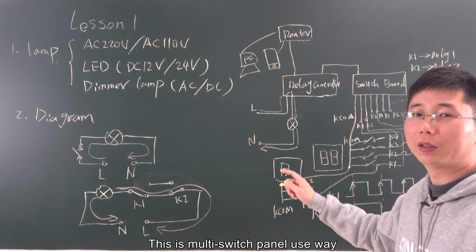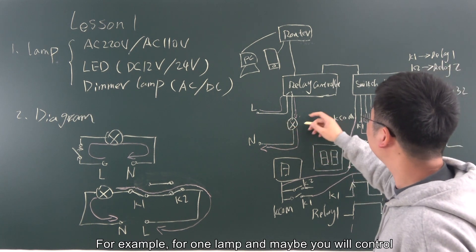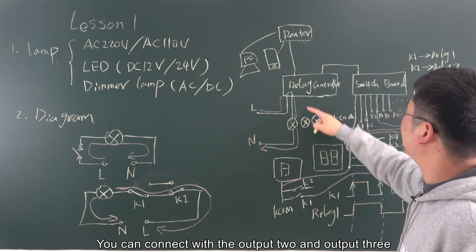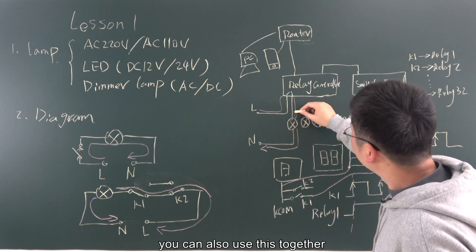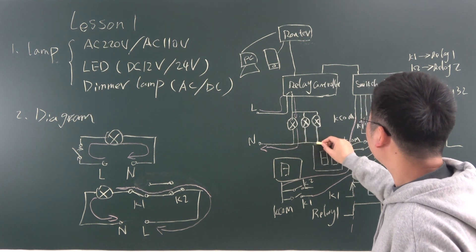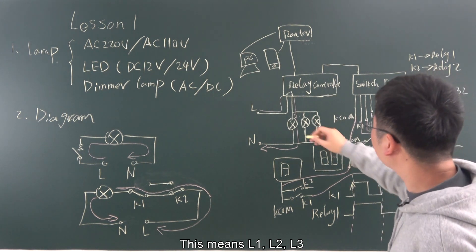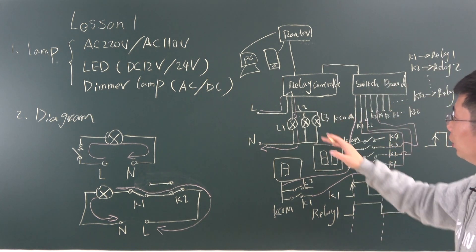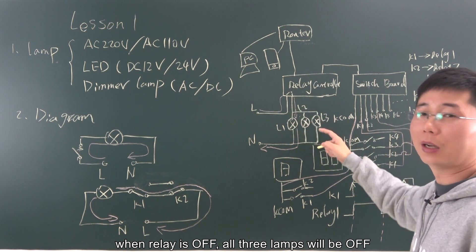Okay, this is multi switch panel to use the way. And if you want to control more lamps, this we have for example for one lamp. Maybe you will control two lamp or three lamp. This is the relay output 1. You can connect with the output 2 and output 3. But if you want to save the channel number, you can also use this together. I can use this three lamp connected together, controlled by the relay 1. This means L1, L2, L3. So when you turn on the relay 1, the three lamp will on at the meantime. And when the relay is off, all three lamps will be off.